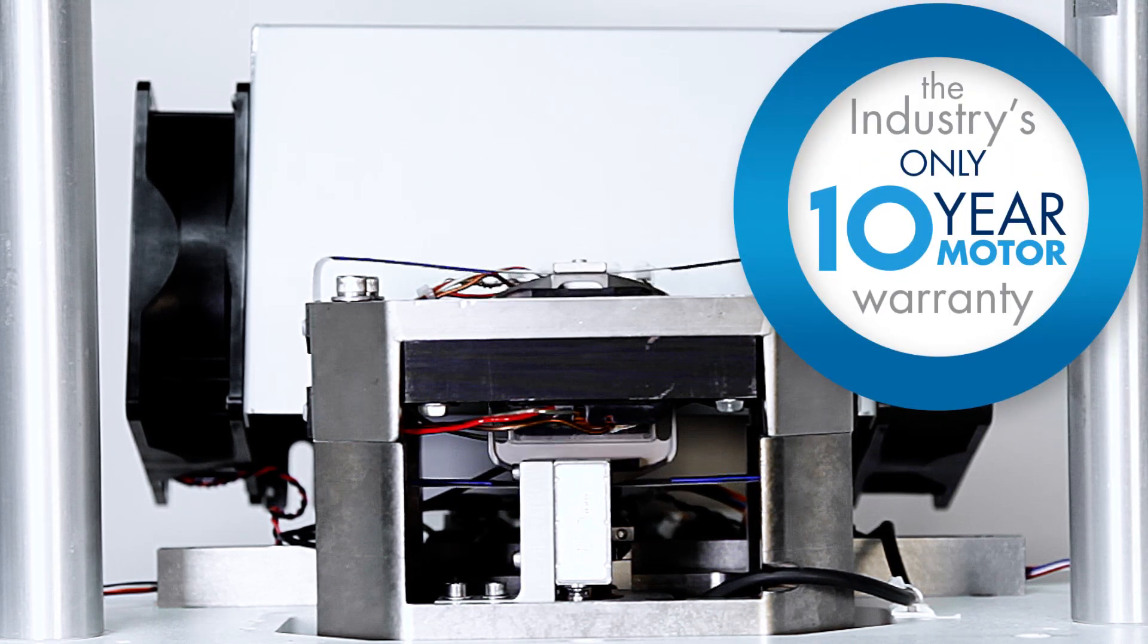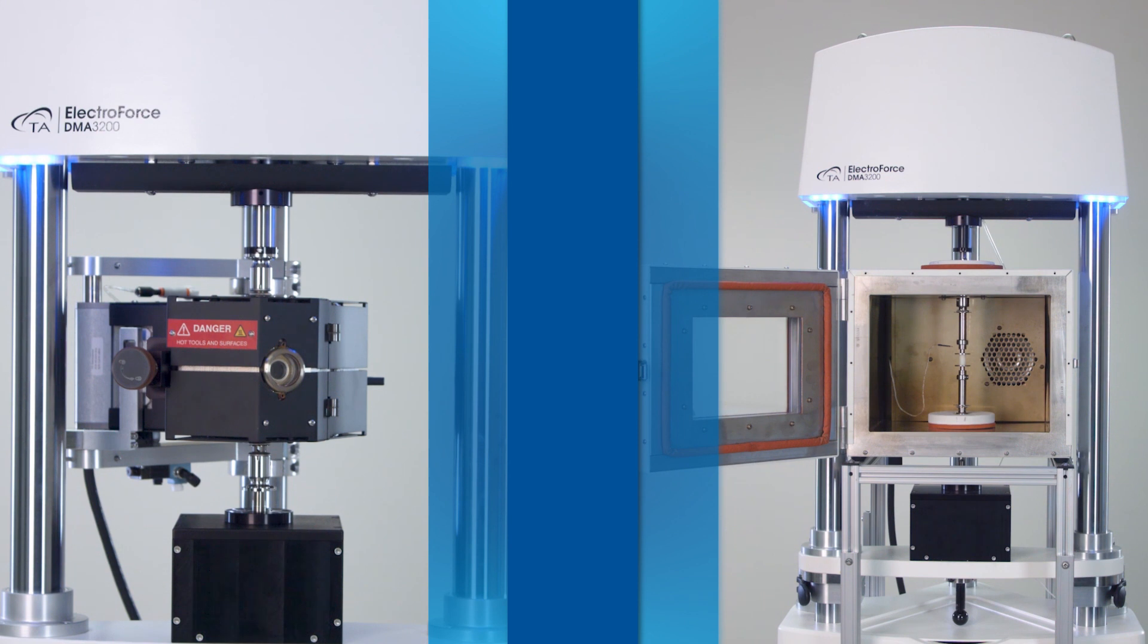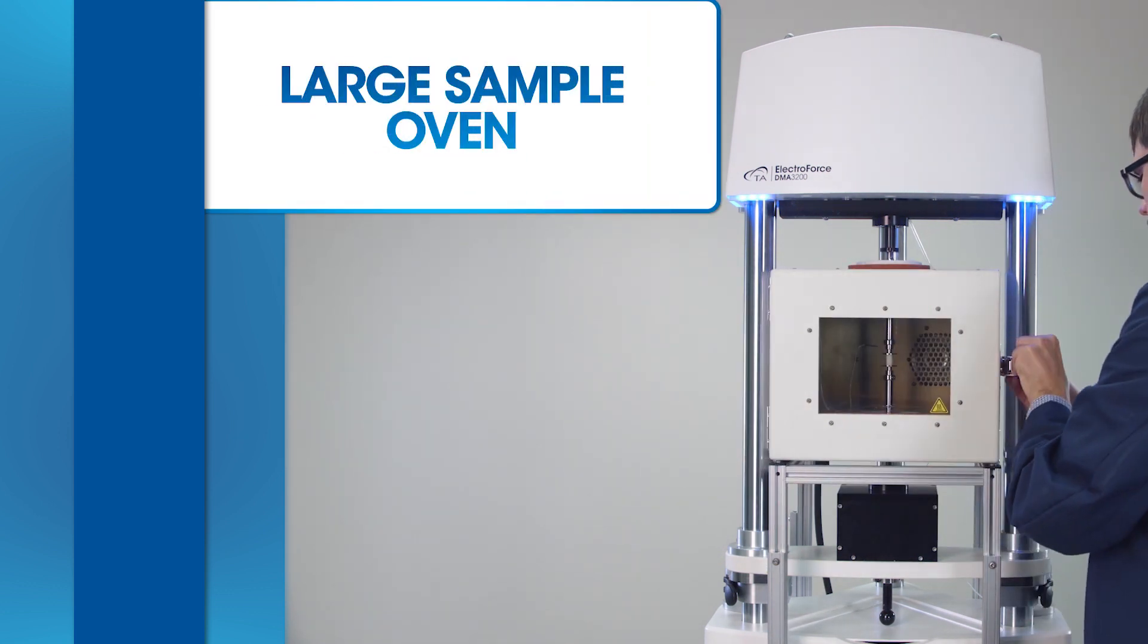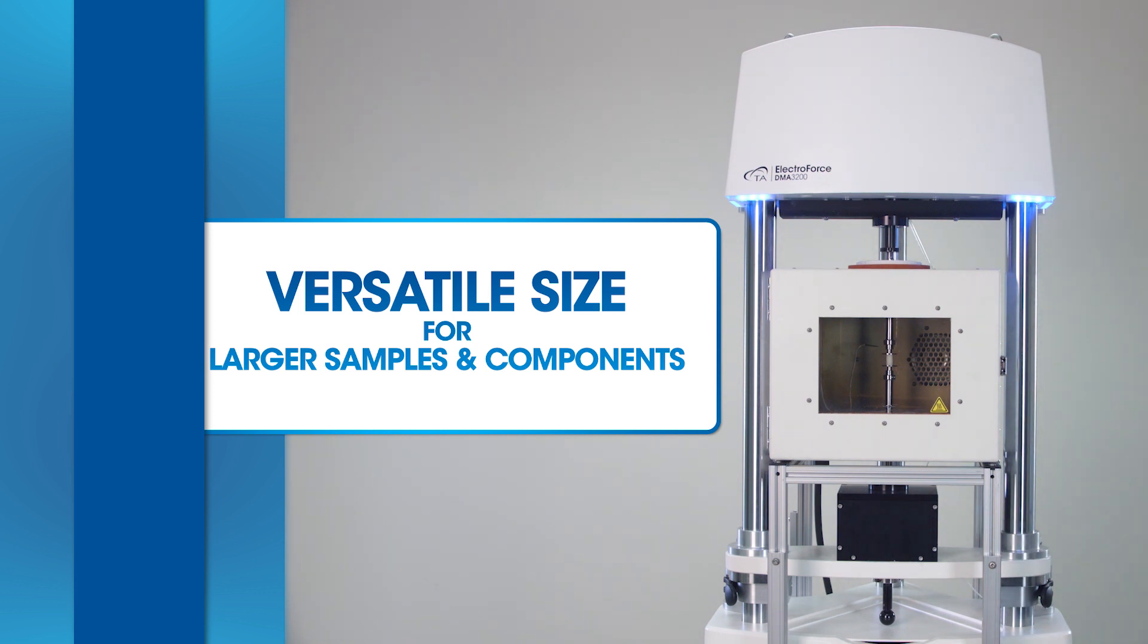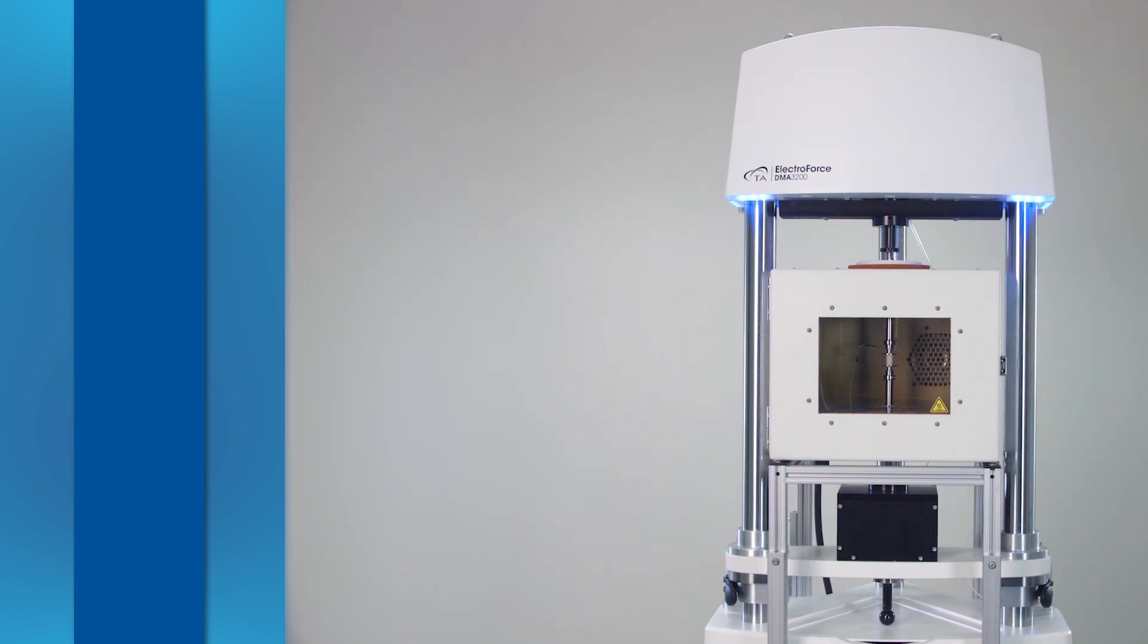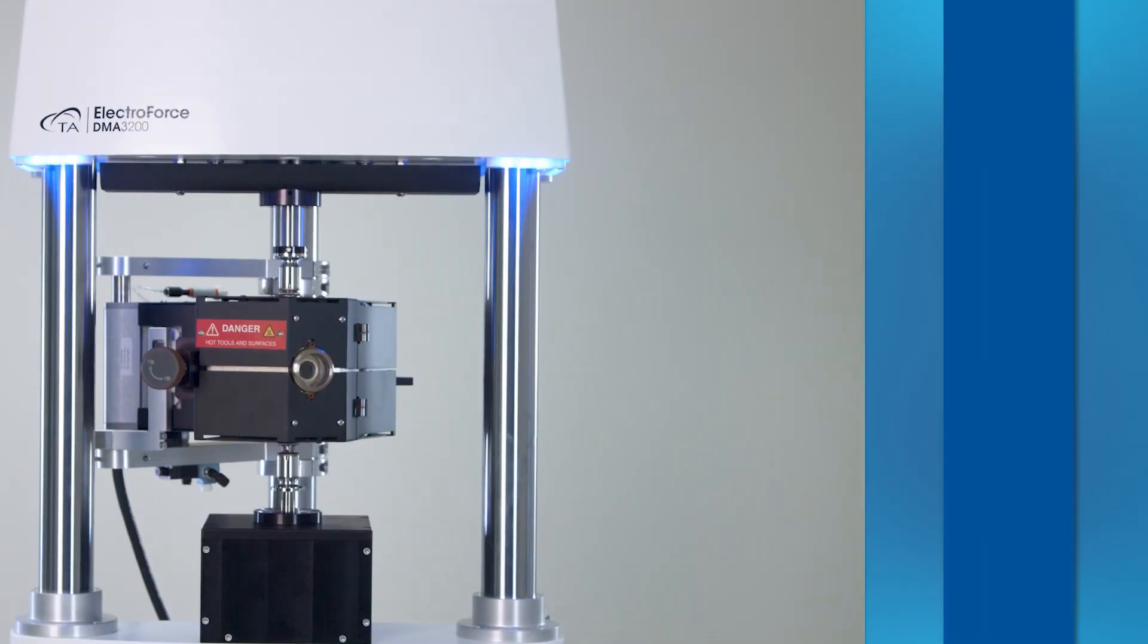The versatile DMA 3200 offers two oven options to enable a wide variety of temperature-based experiments. For larger samples or complete component testing, the LSO oven grants a spacious interior with a capable temperature range of negative 150 degrees Celsius to 315 degrees Celsius.